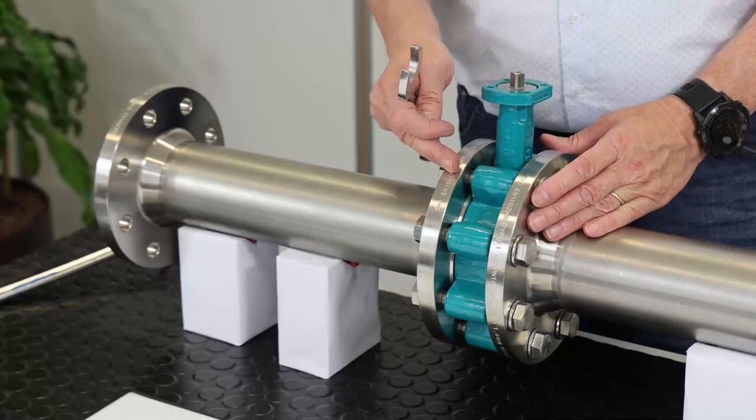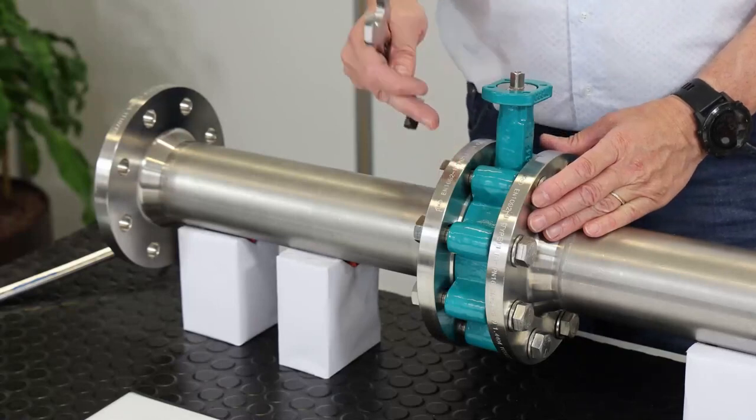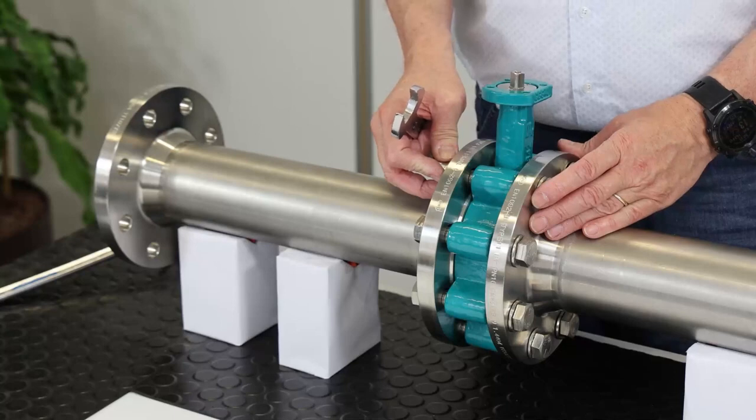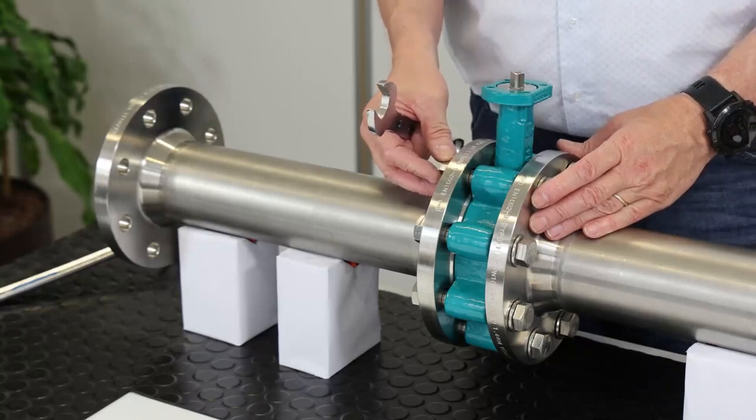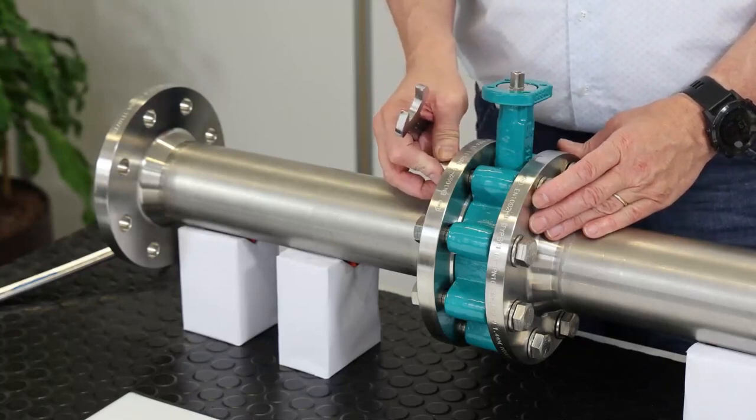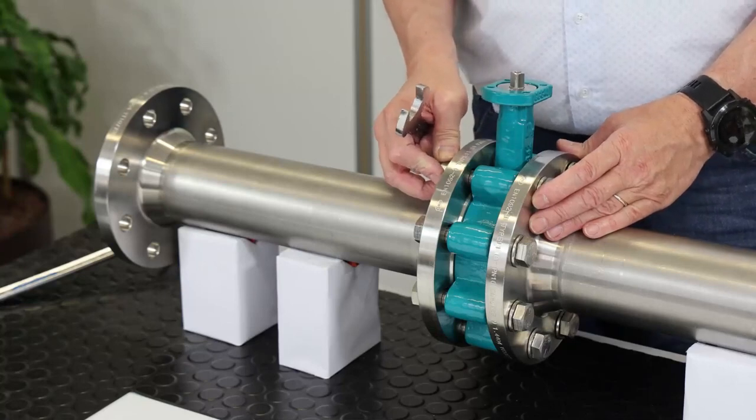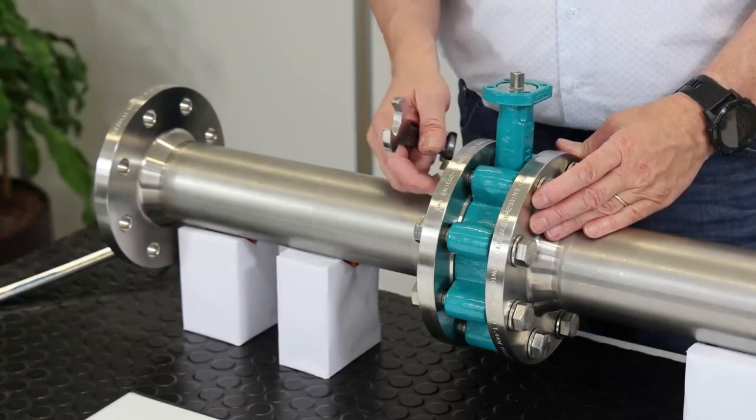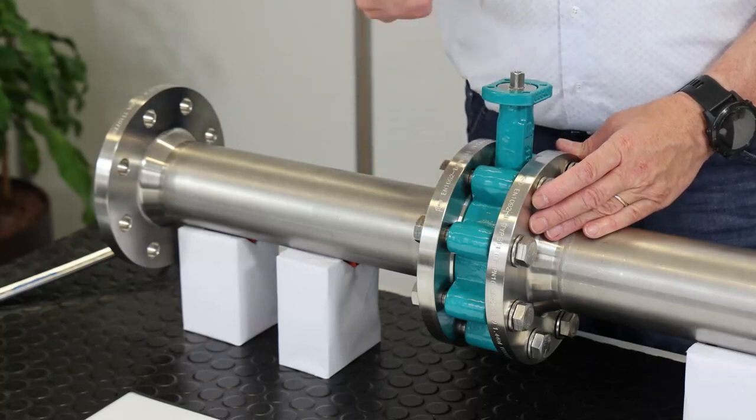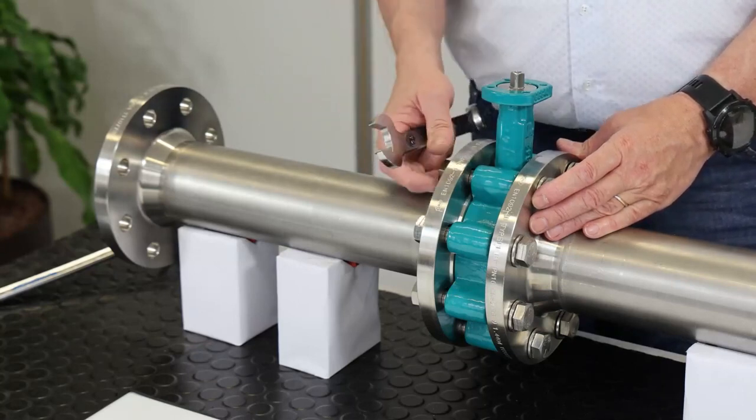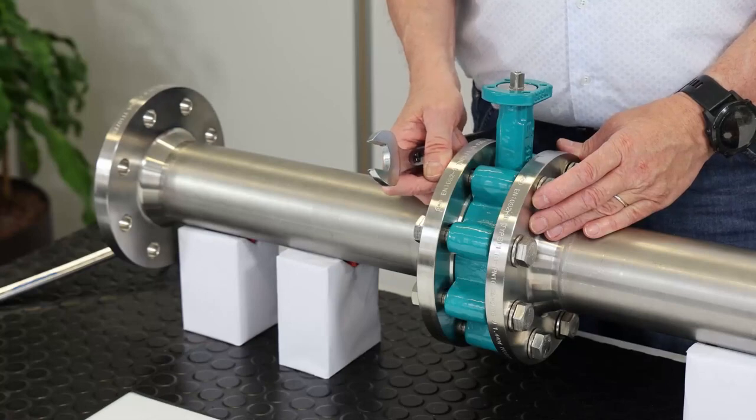On the Teflon-lined butterfly valve, you should consider the tightening torque table that you find in our installation documentation. There you see clearly how much torque you can apply to tighten the screws. If you use too much torque, you will deform the liner of the Teflon-lined butterfly valve.